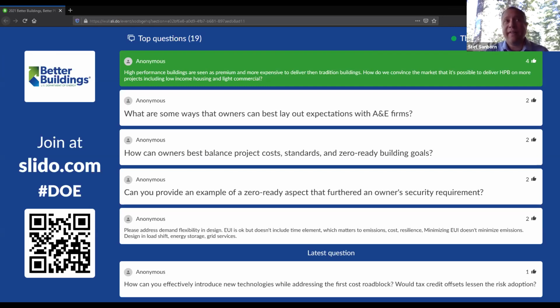On that same project, it's a radiant ceiling classroom building. That tends to be considered a premium product, but because we got the loads low enough, we only needed about 30% coverage of the ceiling with radiant panels.